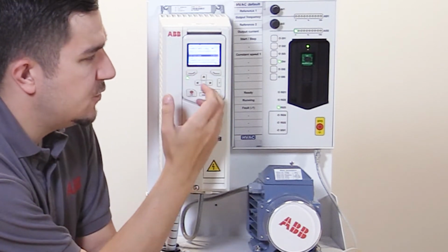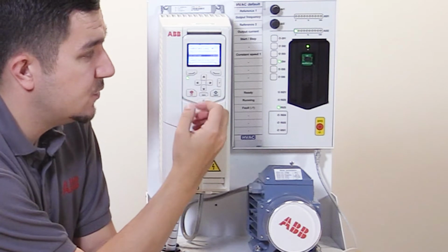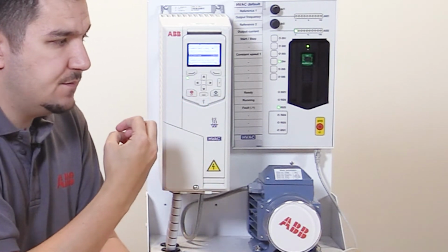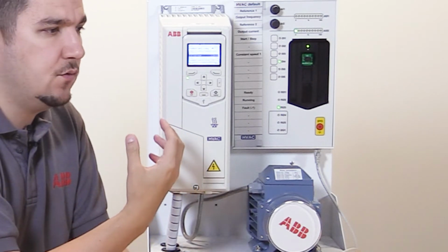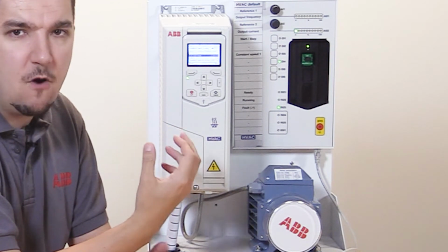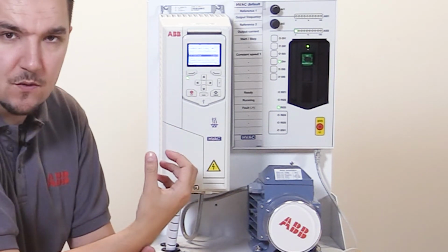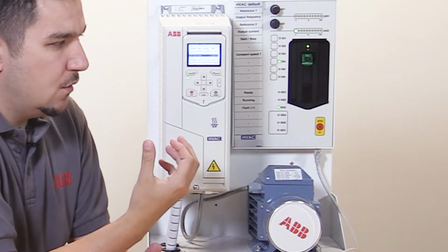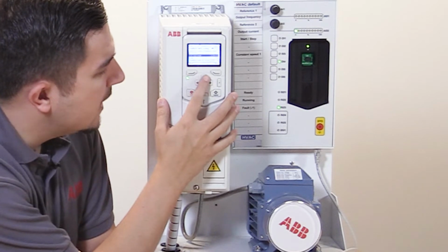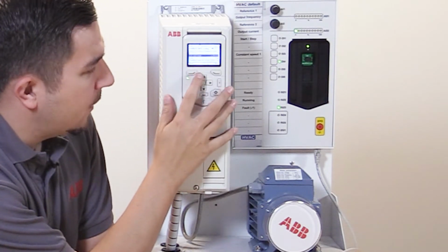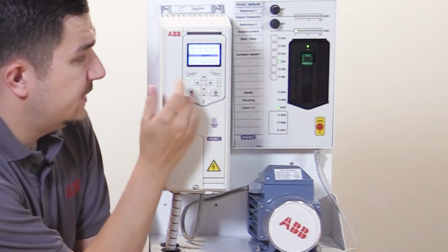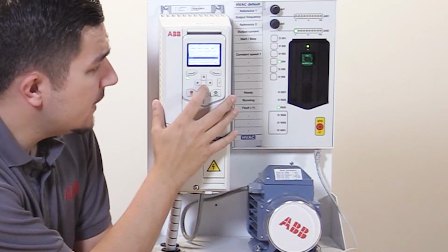And then the first thing we do is we set up the analog input 2 scaling. We have to set that accordingly, more importantly, because the temperature sensor we're using or the flow sensor we're using will have a designated range that we have to adhere to, and we have to make sure that that's set correctly, otherwise we'll be interpreting that incorrectly. So what I've got here is my analog input 2 input range.